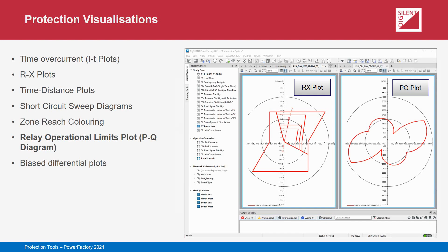The Relay Operational Limits or PQ Diagram plot shows the starting characteristics of distance protection relays in the PQ plane. Typically, a network operator will deal with power quantities rather than impedance, current, or angle quantities when characterizing power flows and load in their network. By representing the starting characteristic in the PQ plane, the network operator is better able to compare actual load data with the starting settings in the network's distance relays, so as to assess whether particular load configurations might cause undesirable operation of network protection relays.